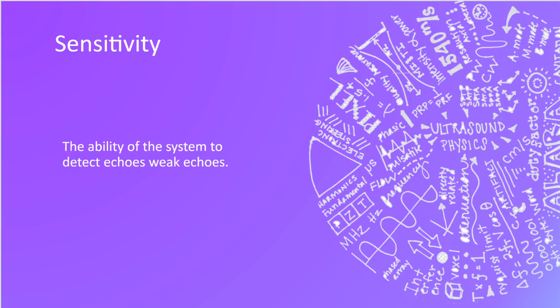So we want to set the machine up in a couple different ways. The first way is to set it up with minimum power, minimum gain. What can we detect with the minimum part of it? And then we want to use normal settings, and then we're going to increase everything to the maximum power, the maximum gain, and observe what our sensitivity to echoes is at maximum. So we want to check at its minimum, normal use, and maximum use to detect weak echoes.